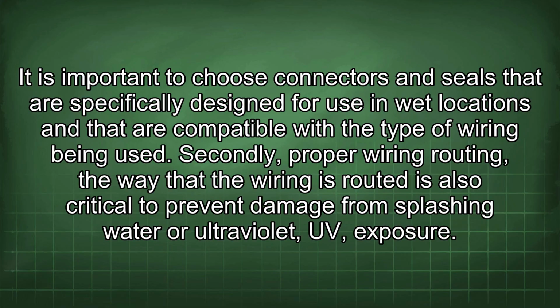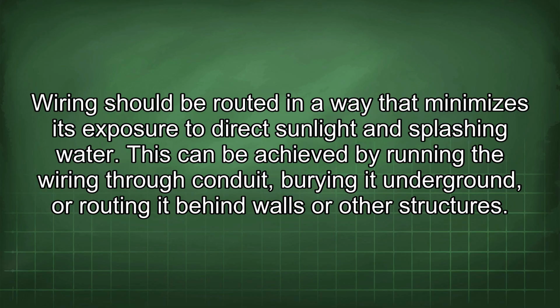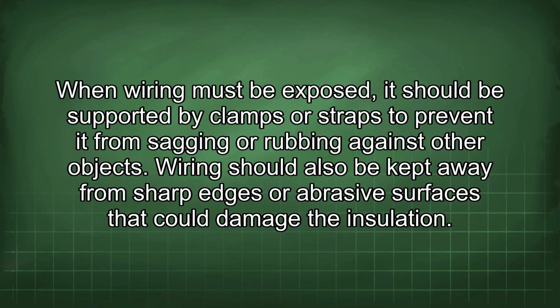Secondly, proper wiring routing. The way that the wiring is routed is also critical to prevent damage from splashing water or ultraviolet (UV) exposure. Wiring should be routed in a way that minimizes its exposure to direct sunlight and splashing water. This can be achieved by running the wiring through conduit, burying it underground, or routing it behind walls or other structures. When wiring must be exposed, it should be supported by clamps or straps to prevent it from sagging or rubbing against other objects. Wiring should also be kept away from sharp edges or abrasive surfaces that could damage the insulation.